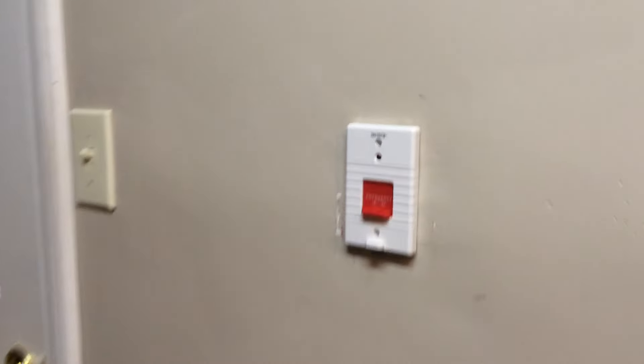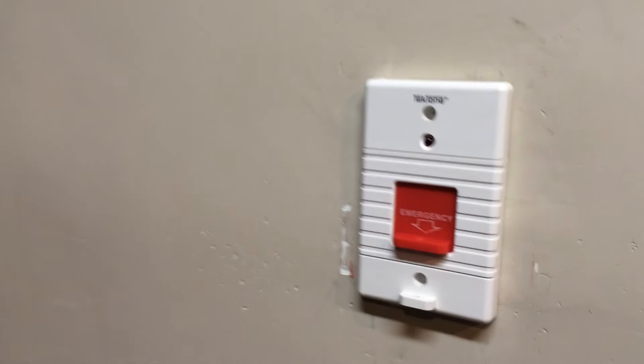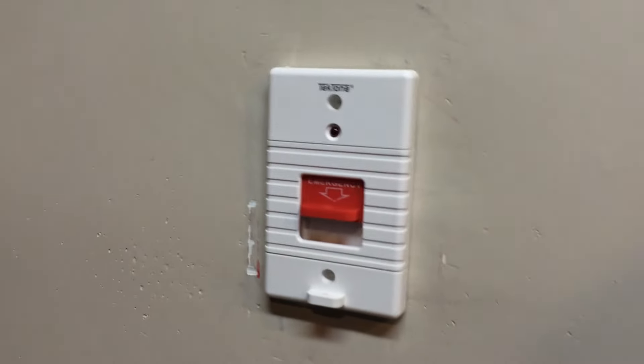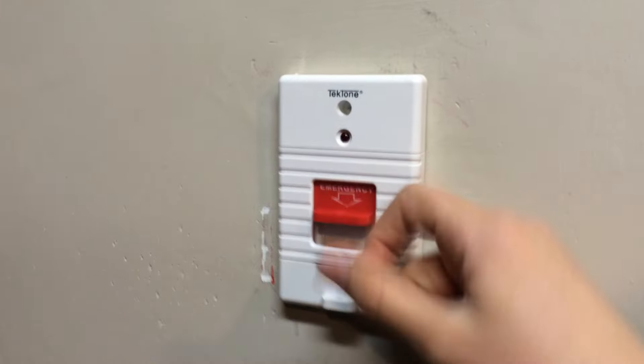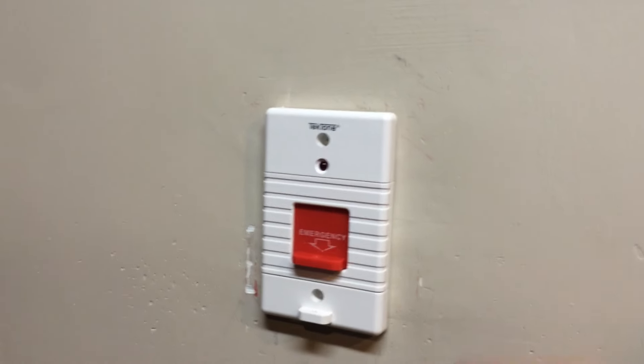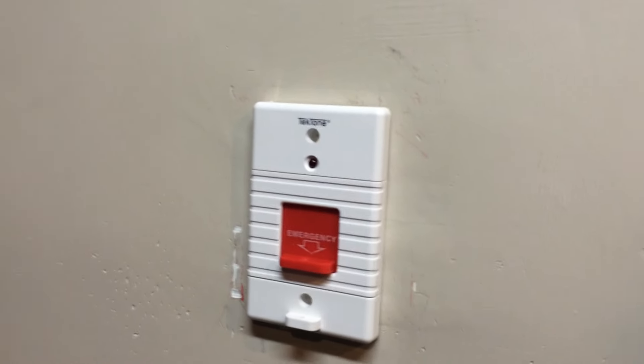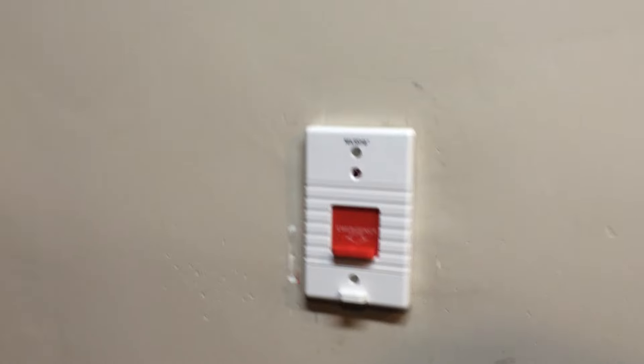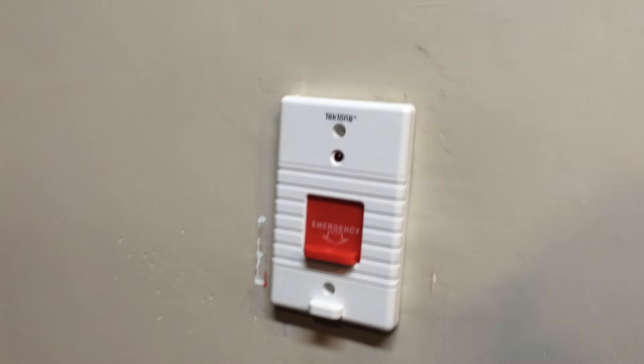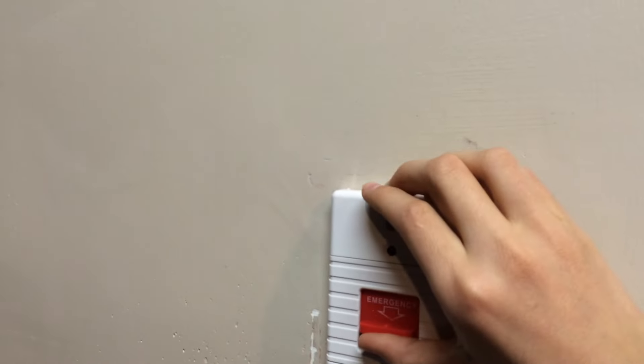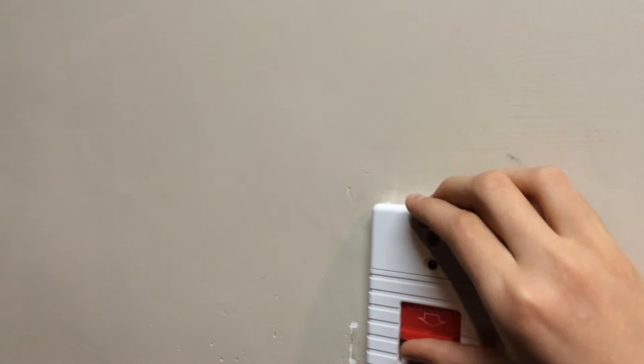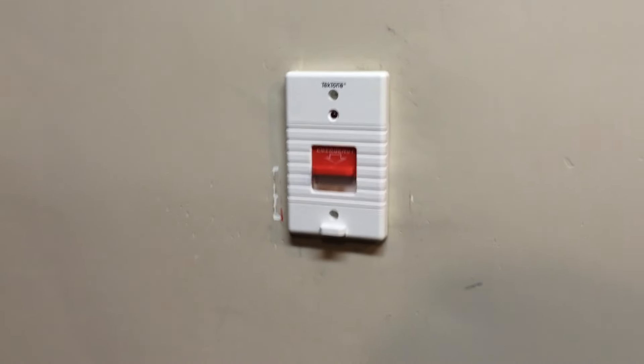Okay, and to reset these, all you have to do is just push it back up. The reason they made it like that is if there's an emergency, you don't want a loud alarm going off for 10 minutes. They want it just so the doctor can come in and push it back up. Like I said, this is completely different from fire alarms.